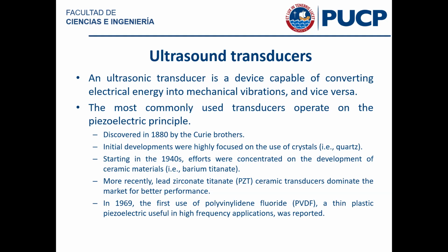That being said, you can find newer technologies in the market, like CMUT transducers, which are capacitive micromachined transducers. These operate under a completely different principle, and this will not be covered in class. I'm just letting you know those exist. On paper, CMUT transducers have better performance compared to their piezoelectric counterparts. In practice, it's questionable how much better they perform, but still, it's another way that ultrasound can be generated.